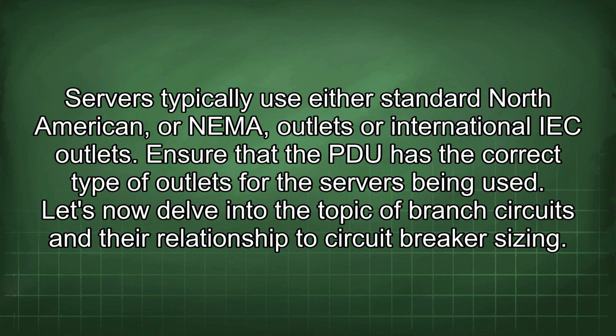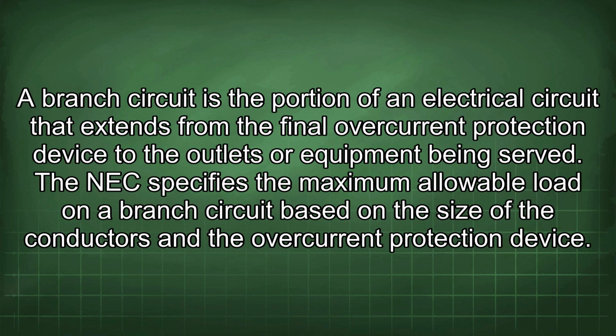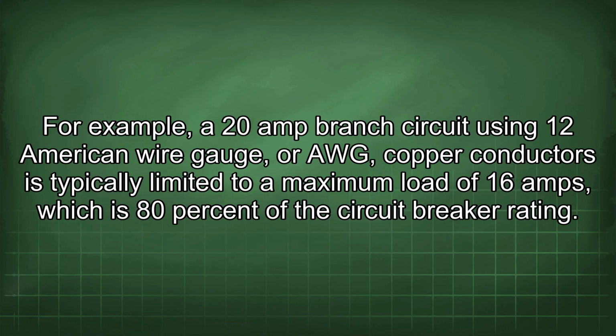Let's now delve into the topic of branch circuits and their relationship to circuit breaker sizing. A branch circuit is the portion of an electrical circuit that extends from the final overcurrent protection device to the outlets or equipment being served. The NEC specifies the maximum allowable load on a branch circuit based on the size of the conductors and the overcurrent protection device. For example, a 20 amp branch circuit using 12 American wire gauge, or AWG, copper conductors is typically limited to a maximum load of 16 amps, which is 80% of the circuit breaker rating.